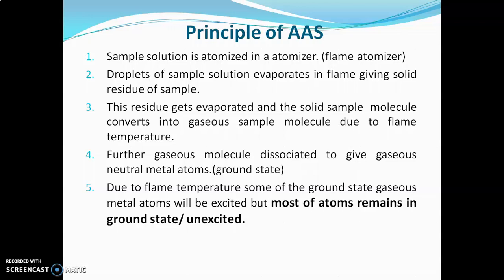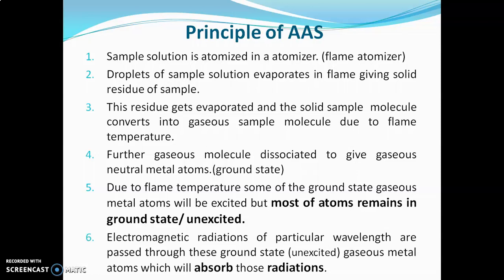The excited atoms show emission of radiation and they are studied by flame photometry, but the atoms which are at the ground state or unexcited state are studied by AAS. Electromagnetic radiations of a particular wavelength are then passed through the ground state unexcited gaseous metal atoms, which absorb those radiations. This absorption of radiation by the gaseous metal atom is the basis of AAS, and the absorbed radiations are measured by the detector.